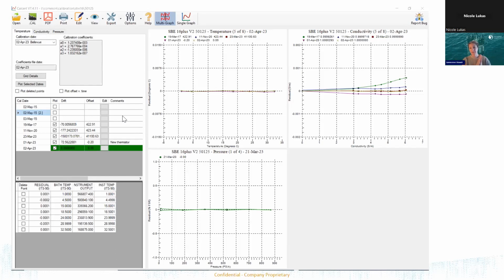So these pre-cruise calibrations indicate the state of the sensor before the data was collected. So when you get a fresh instrument, either freshly back from service or you've newly purchased it, you have a set of these pre-cruise calibrations, and it's just the state of your instrument. The way it is today. You can go and use it, and then when you send it back in and get the post-cruise calibration, it really indicates how much that sensor has changed over the time that the data was collected. So if there is a slope change or an offset change, either of those can be added to your calibration coefficients to correct your data.